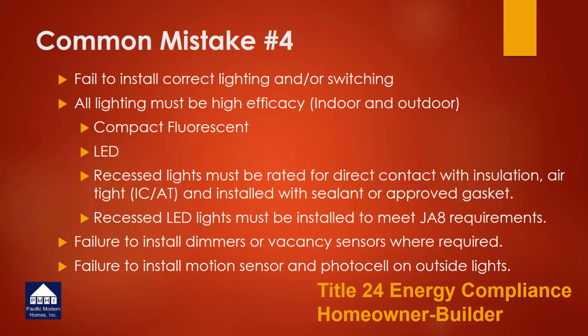Now, recessed light fixtures, I said before, have to be rated for direct contact with insulation or airtight. This includes light fixtures that are between 2 floors. So you have a 2-story house and you have recessed light fixtures on the first floor. They have to meet this requirement as well.